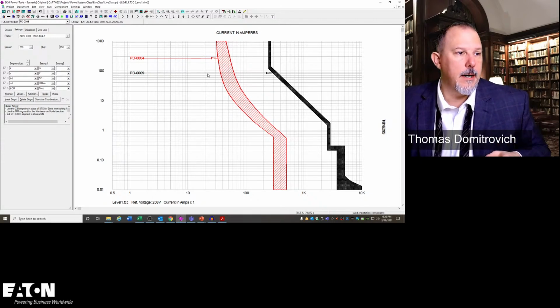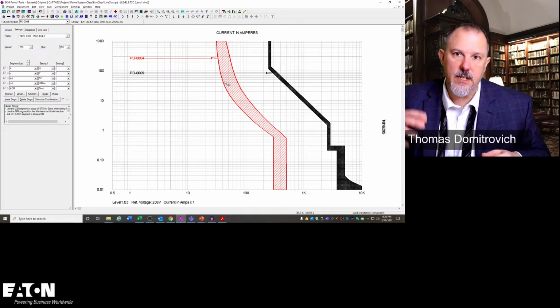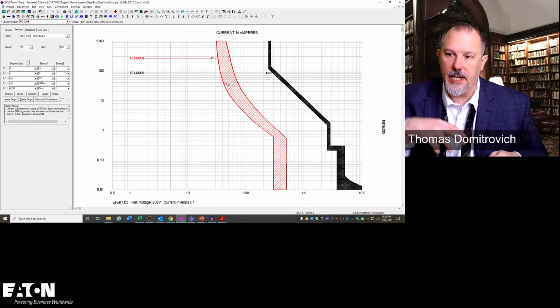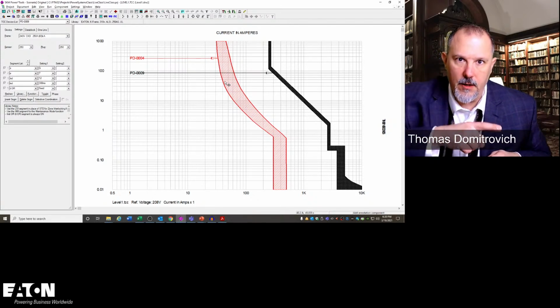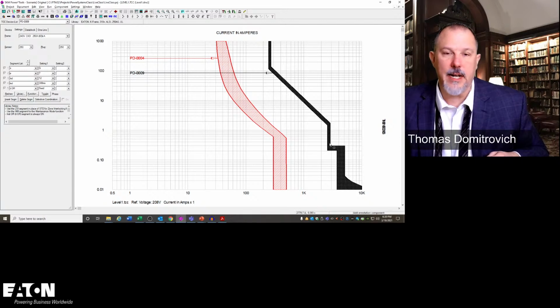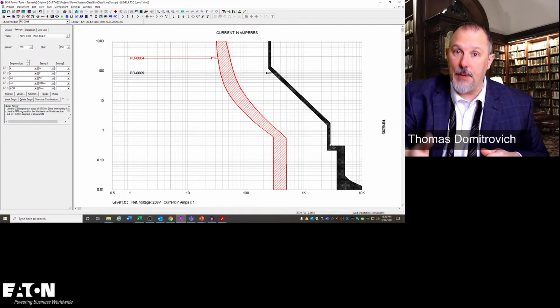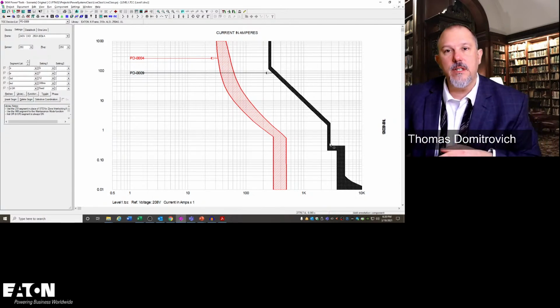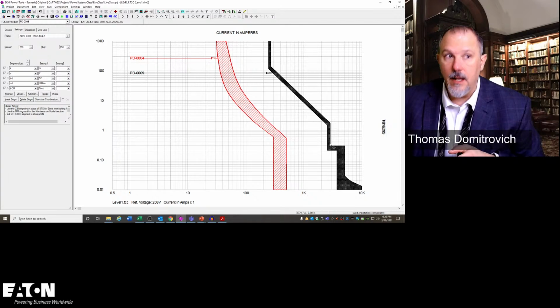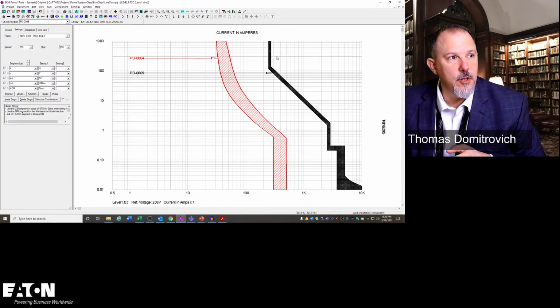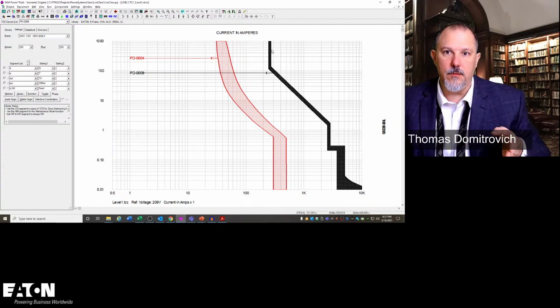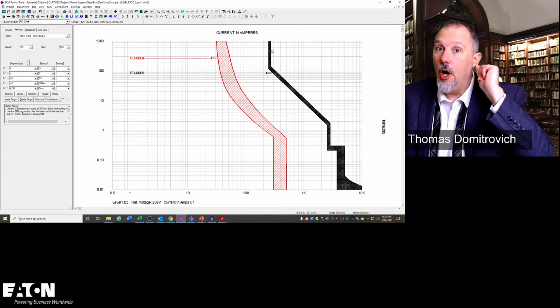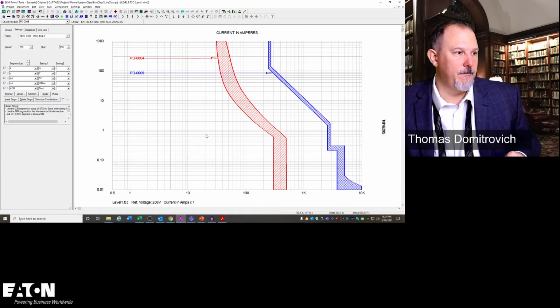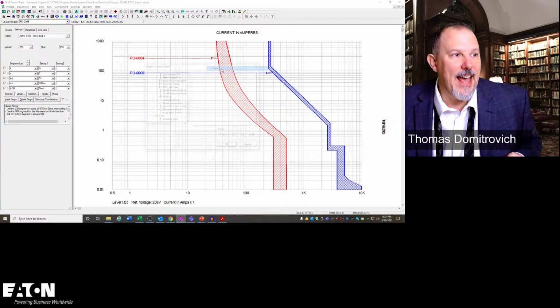Okay. There's different ways to address the selective coordination in regard to this. I can reduce the fault current by adding impedance into my system. I can increase the size of the upstream overcurrent protective device. But when you start increasing the size of the upstream overcurrent device, make sure that this long time pickup can be adjusted down to where you need it to be. And here is another solution. So I'm going to add a fuse. Ryan Jackson brought it up.